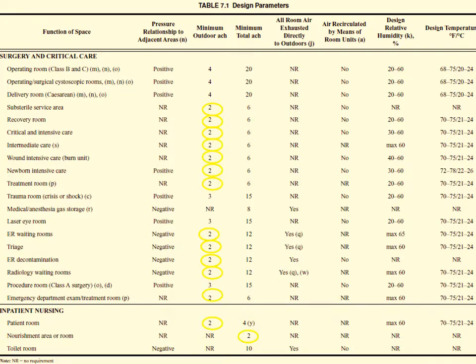Anyone who's used this table knows this number. It's the most common number in the table, and that number is 2 air changes per hour. That's the outside air ventilation number. We use that for most spaces in hospitals.